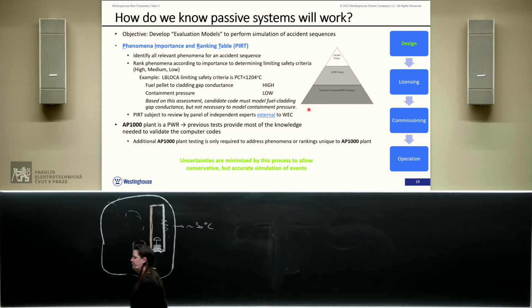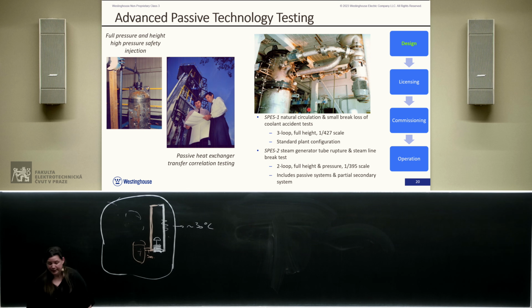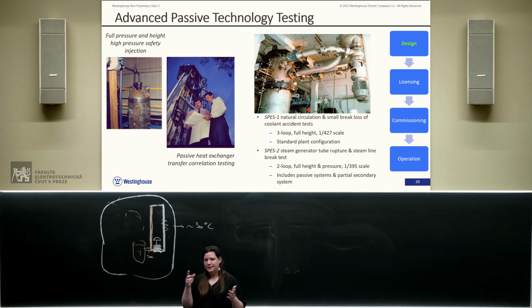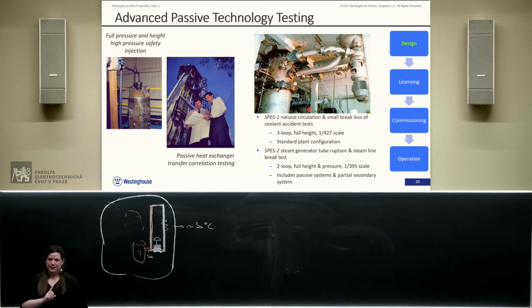For each area of medium or high importance where I feel I don't know enough, I'm going to do a test: a test to define a heat transfer correlation, a test to verify I can predict how much flow rate I'll have in the loop based on the resistance in the piping. So first, you do testing on just one specific thing.